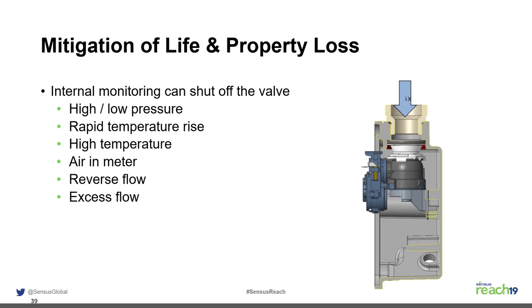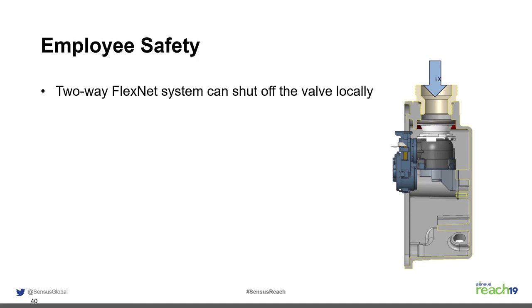If a meter is tampered with and removed, air is detected in the meter and the valve shuts. When the meter is reinstalled, gas won't flow until the utility is contacted and the valve is manually reopened via the optical port — the only way to open it in North America. In Europe, utilities are allowed to open valves remotely after the homeowner follows a defined protocol. The meter can also measure leak flow while the valve is shut off.